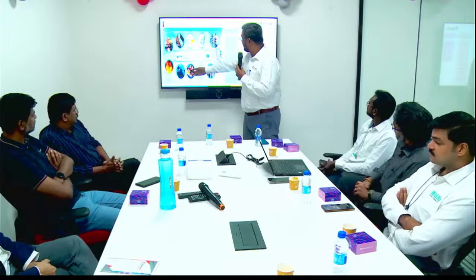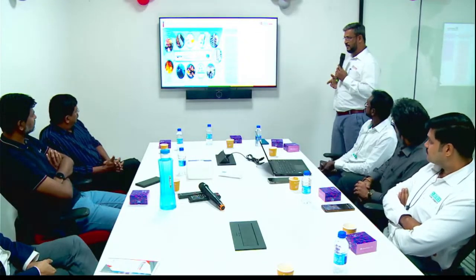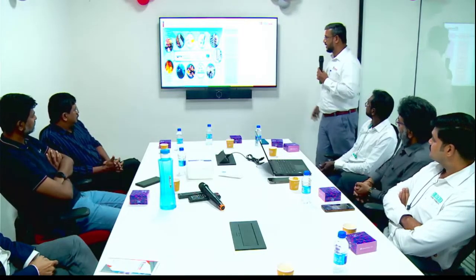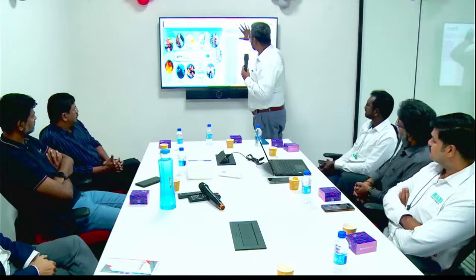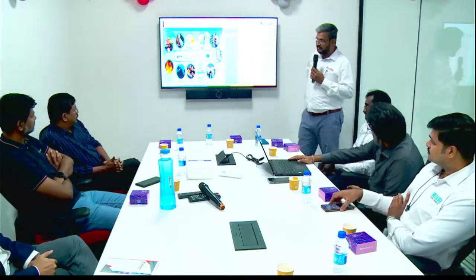Likewise, for EMC, we should keep the electrical cable away from the data cable, at least a foot. These are the recommendations we have to follow. Only then can we achieve consistent performance.